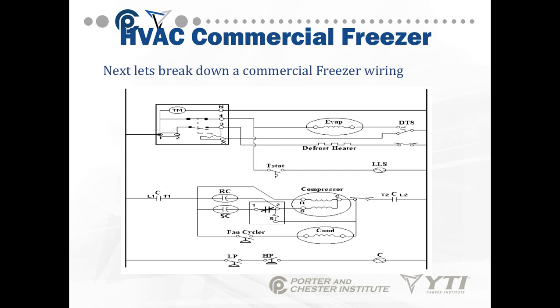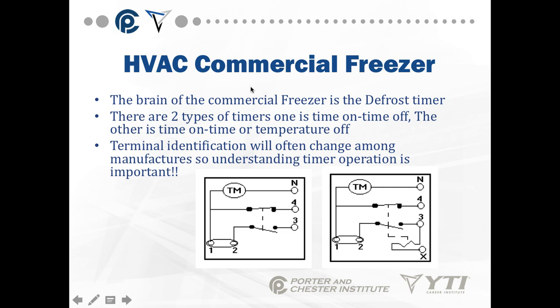This is a commercial freezer wiring diagram. It's a little bit different because we do not want ice to build up and cause problems on the evaporator fan or evaporator, so we have to have defrost up here on the left-hand side. We use a defrost time control. There are two types of timers: one is time-on, time-off; the other is time-on and temperature-off. The one on the left is time-and-time; the one on the right is time-and-temperature. Notice the X terminal.